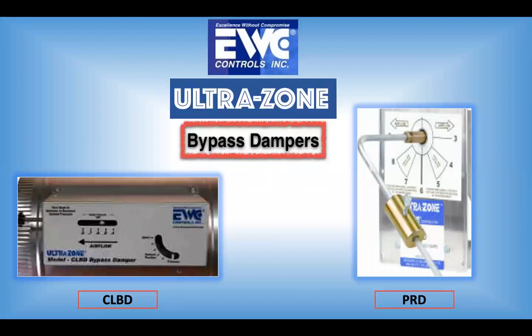So what we're doing is holding the bypass damper blade closed by means of a magnet. Once we reach or exceed the static that is set on our bypass damper, which is done with a thumb screw, and you'll notice the scale on the left of that faceplate, we choose our bypass, and once we exceed that, the magnet releases that blade, and now we're being held by the spring. And the spring is there to keep that damper blade from going all the way open and only going open as far as it needs to relieve static, relieve excess airflow.